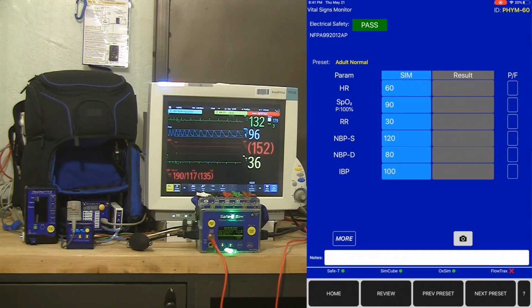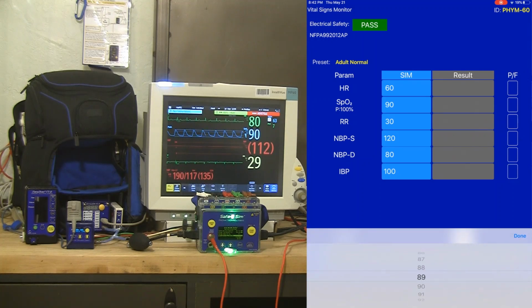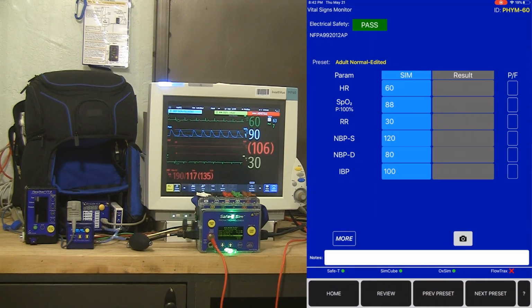Be aware that you don't have to stick with the simulated values on the left-hand column. If you need to adjust those based on a manufacturer requirement, let's say that SpO2 requirement is 88 instead of 90, you can actually change that simulated value. You're not stuck with it, and you can customize as you go.